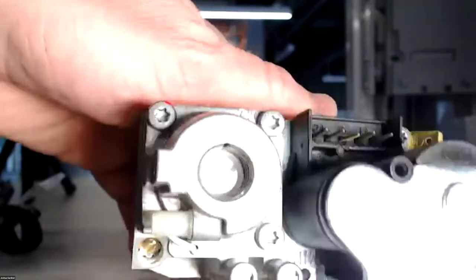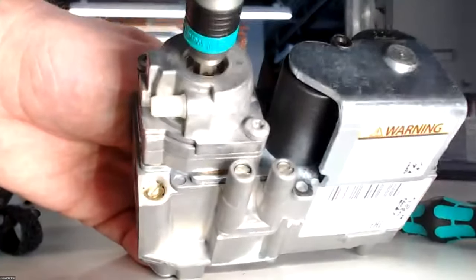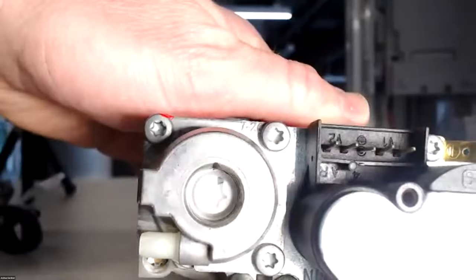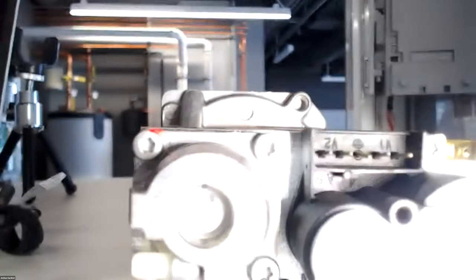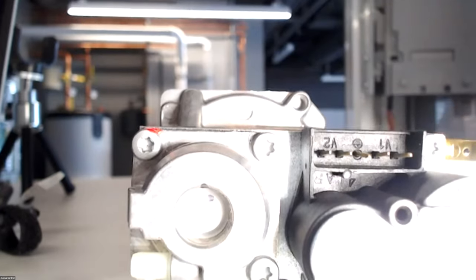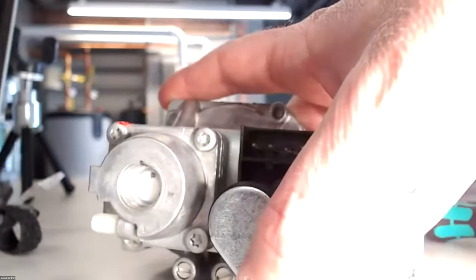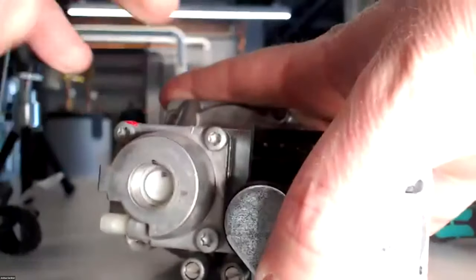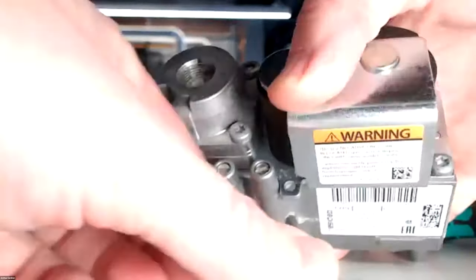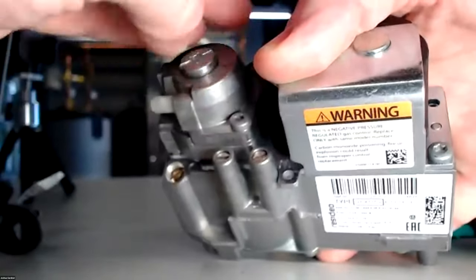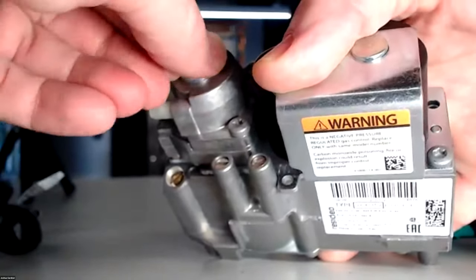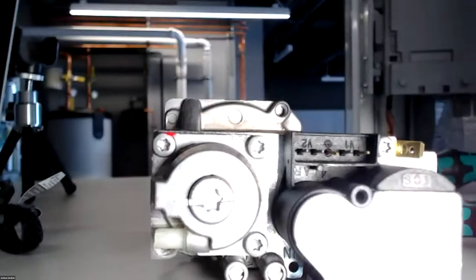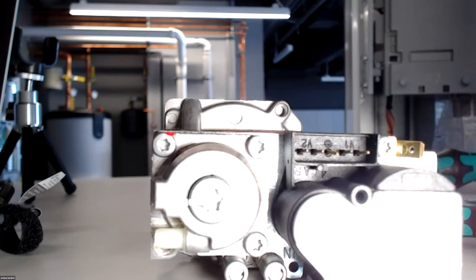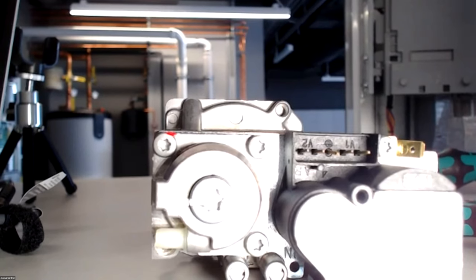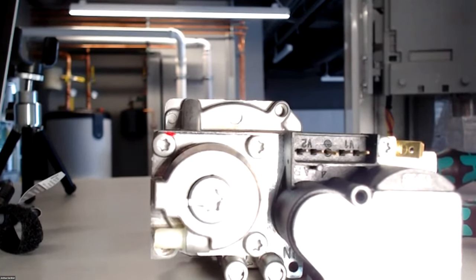All right, it's a very fine adjustment. You'll turn this probably about that much, and you'll see it move probably 2 points. So you just gotta be careful on that. So you're in low fire, you get it dialed in with this, and then that's it. You don't touch that throttle again, we leave it wide open, put our cap back on, we go to our high fire settings, confirm that's good. And once we set this, that high fire is usually always right in target. If it's not, call us and we'll go through some other stuff. There's probably another issue going on, but that's how you adjust that offset.